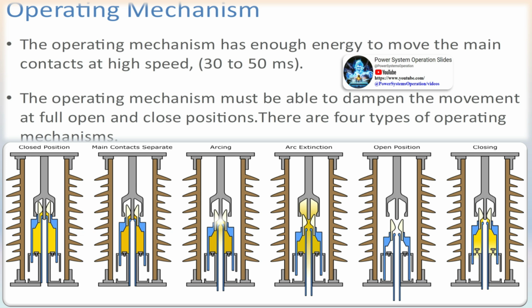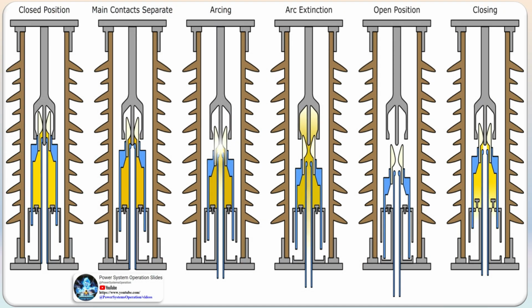Requires regular maintenance. Requires special consideration in regions with altitudes higher than 3,000 feet mean sea level, due to the lesser density of the dielectric gas, atmospheric air. The poor dielectric properties of air, as well as secondary factors such as humidity, pollutants, salt, and moisture, means that more space is needed. SF6 gas.